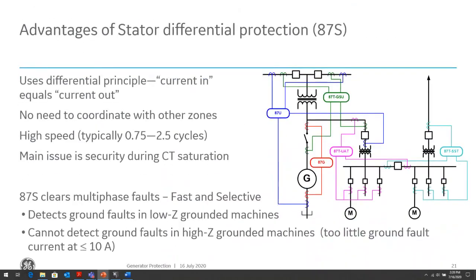And the type of protection we use to be able to do that is the differential protection, or 87S. I don't know if everybody's familiar, but the differential principle is basically looking at currents entering the generator and currents leaving the generator. Under normal loading conditions, or external fault conditions, current entering the generator at the neutral CTs of the generator and leaving at the terminal CTs of the generator are equal. So when we say differential, we're doing a subtraction between those two currents, a vectorial subtraction. For faults outside the zone of the generator, the current in should be equal to the current out. So we have zero differential current and we will not operate.